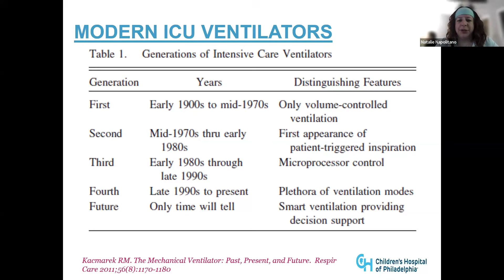But how these devices are driven and the guts of them are really important when you're trying to choose a device. Their gas delivery is either a compressed gas, which is the most common for ICU ventilators, and it's dependent on having medical grade oxygen and air sources at a high pressure. Generally 40 psi is what all of these devices are calibrated to want coming into them. So if they don't get 40 psi of both gas sources, you will have alarms, and it won't be able to function as it should. With this, you get more accurate oxygen monitoring, but it does limit your mobility and your locations of use.